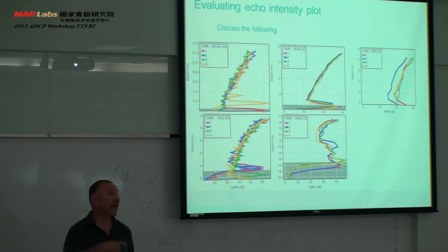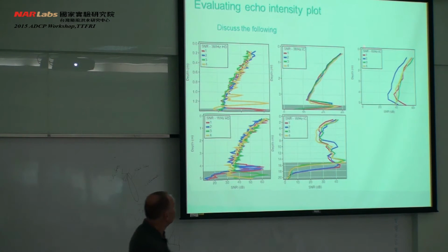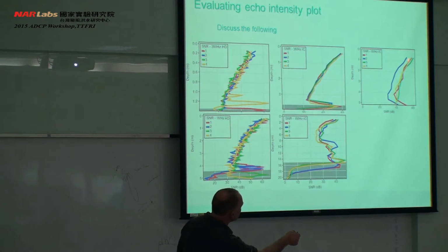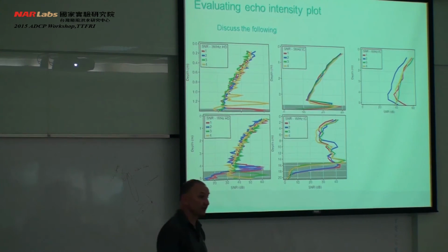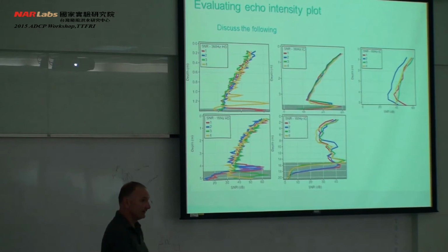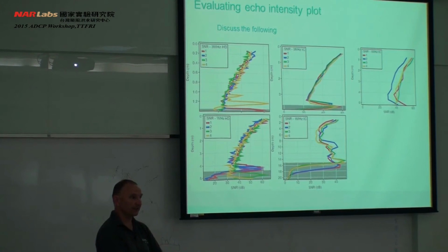Air. It's the air entrainment around the transducer. Okay. Now, when we get this offset, 99 times out of 100, that will be an air bubble or a pocket of air around the transducer. If you see that, lower your instrument down in the water.